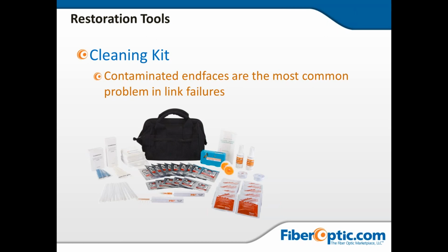While inserting the connector, it scrapes a lot of the contaminants off the inside sleeve. So I really recommend those other swabs for cleaning the inside sleeve. Even if there's no connector in there, you can piston a swab in and out of the mating sleeve and clean it up, and repair what could potentially be causing some of your problems with a bad mating sleeve.